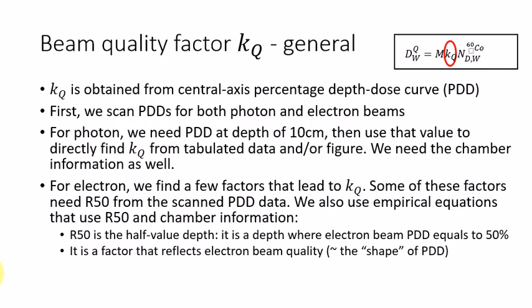In general, KQ is obtained from central axis percentage depth dose curve, or PDD. So before we do any TG51 point dose measurement, the first thing we need to do is scan the PDDs for both photon and electron beams in a water tank.